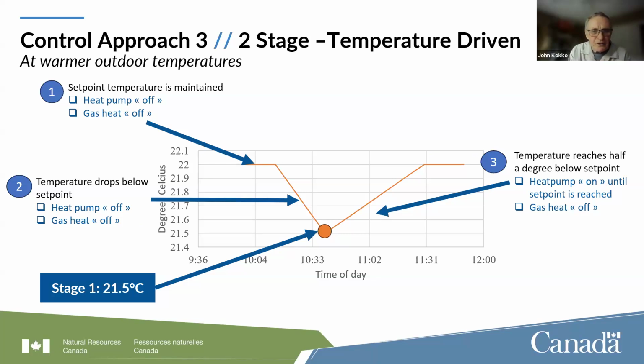Control approach number 3, two-stage temperature driven. So what this does is, in, let's call it warmer temperatures, the house is at a set point of 22. It starts to cool off. We've got an offset of about half a degree, so at 21.5, we say, okay, let's bring the heat pump on, bring the house back up to temperature. As long as the heat pump is able to bring it up to temperature, we're all good. We use heat pump only, and it turns off. Then we start that cycle all over again.